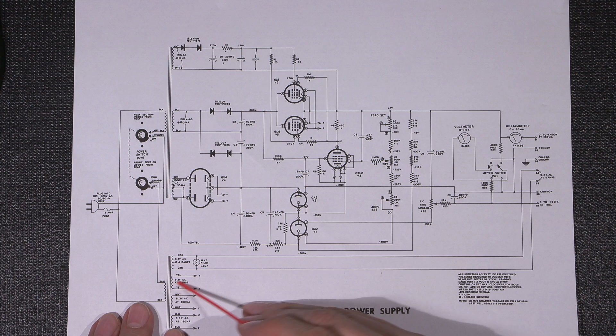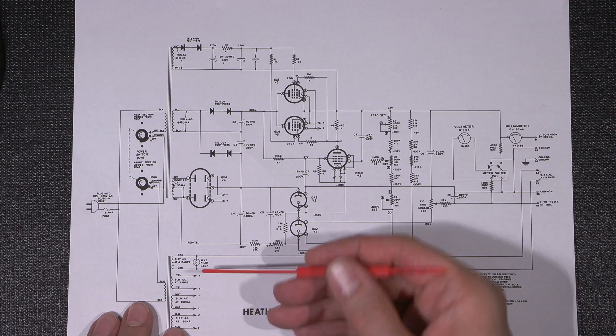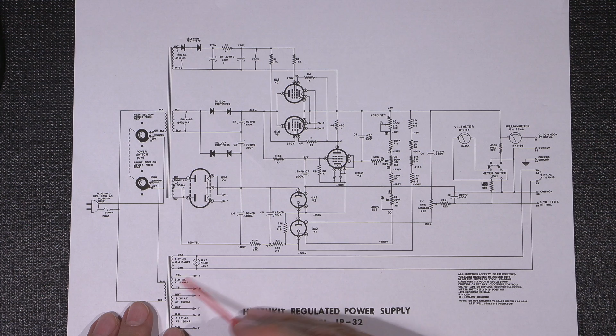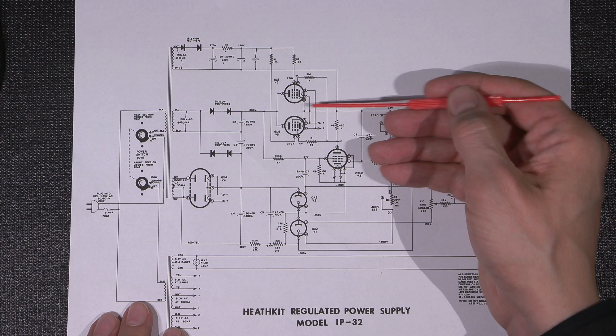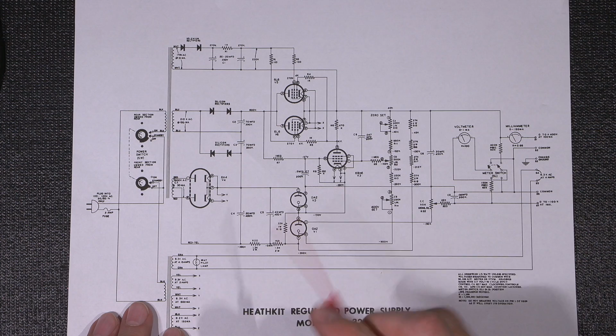You can see we have AC here on a filament winding, and those filament windings are attached directly to our DC output. That can be tricky for those new to this. This AC filament winding is isolated from everything else—not attached to anything. So even though we have AC attached to the cathodes here, there's no circuit for that AC to travel, so it's virtually invisible on this line. We can have AC here and DC at the same time, yet because it's on its own isolated winding, it's invisible at the output.